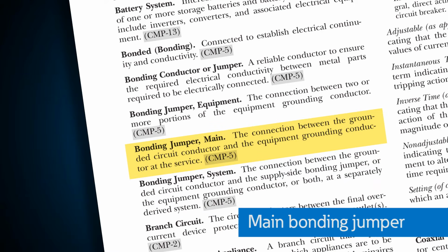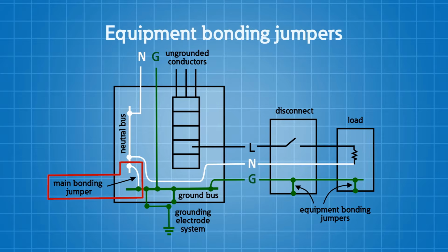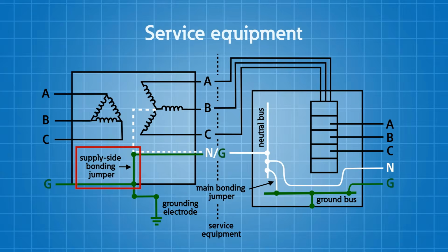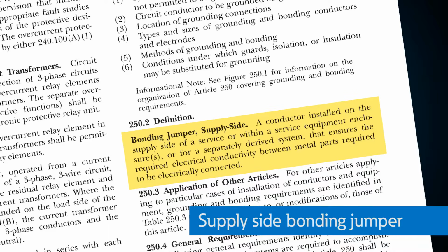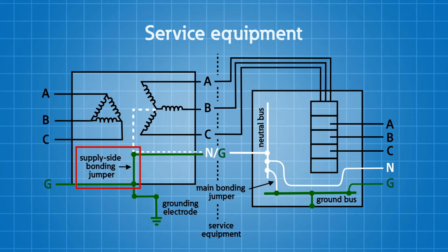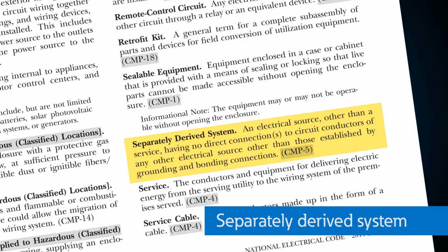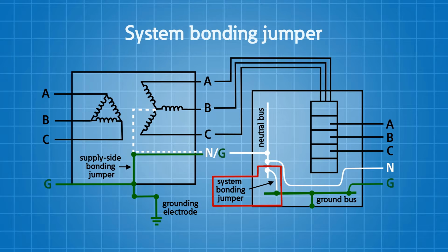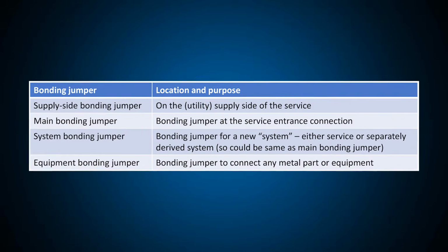One of those is the main bonding jumper. The connection between the grounded circuit conductor and the equipment grounding conductor, or the supply side bonding jumper, or both, at the service. So this is your main bonding jumper, that point where we pull both of those conductors, or those systems, together. Now your supply side bonding jumper, this is the conductor that's installed on the supply side of the service, or within the service equipment enclosures, or for a separately derived system, that ensures the required electrical conductivity between the metal parts that are all required to be electrically connected.